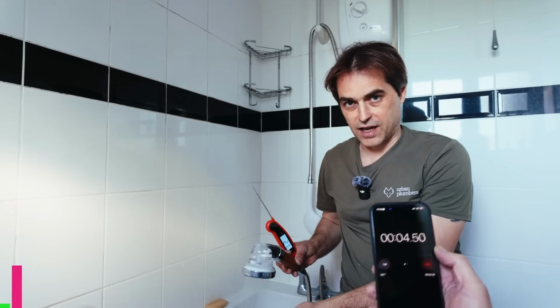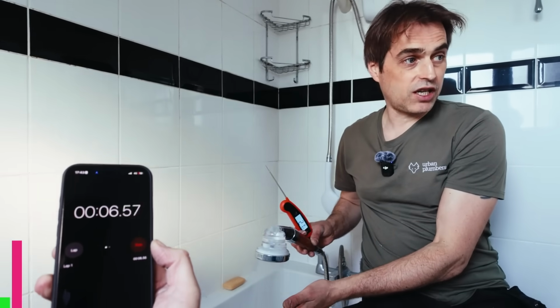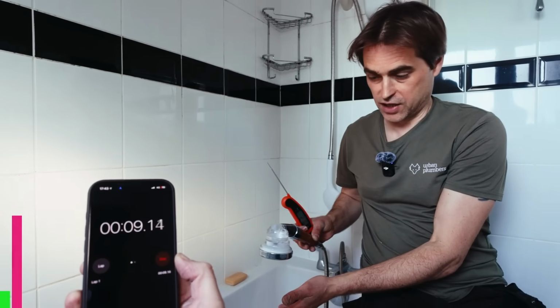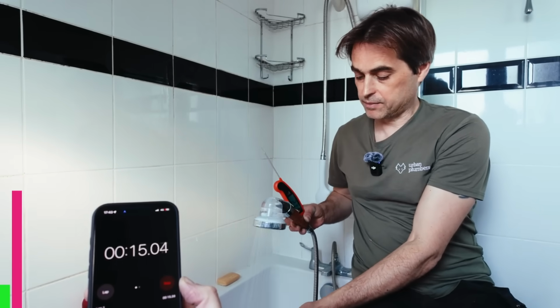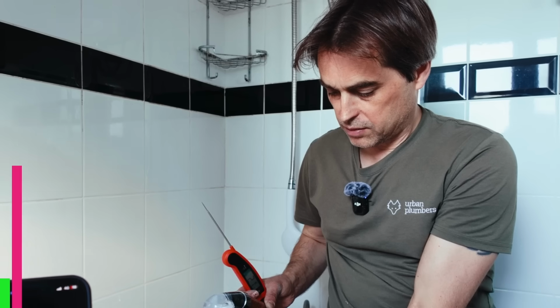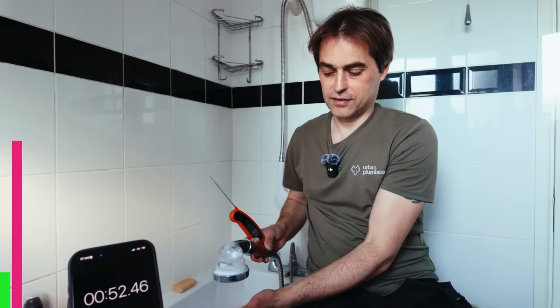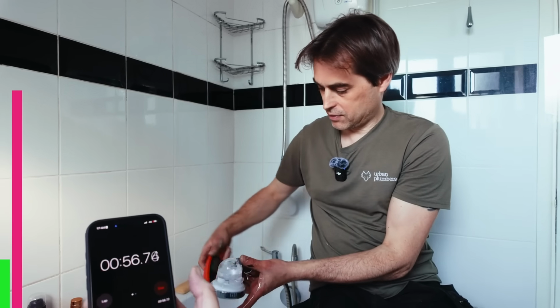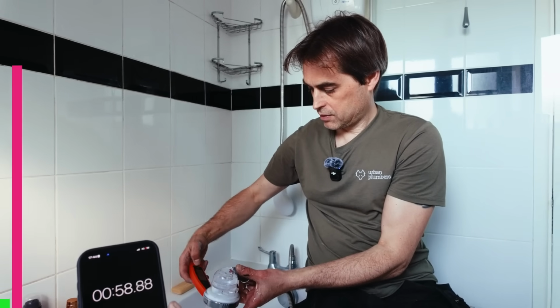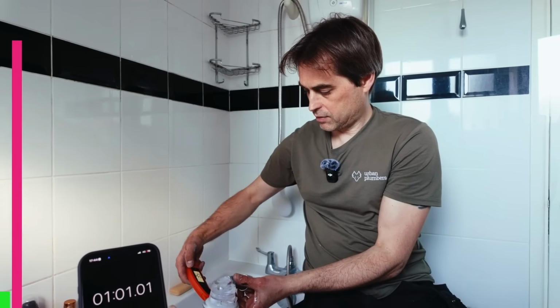Start the timer. Timer started. Let's see if we get any hot water. And we're also gonna check if that heat pump kicks in to help us when the sensor reads the drop on the plate. Oh, it's getting warm. I'm getting something. Oh, it's taken 50 minutes, 50 seconds to come through anyway, so yeah. Really the timer starts now, because now you jump in, so we'll shave a minute off of the shower time.